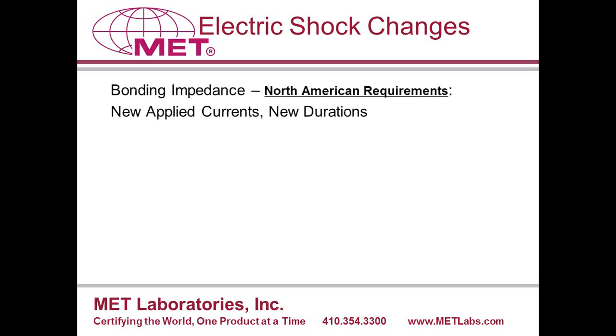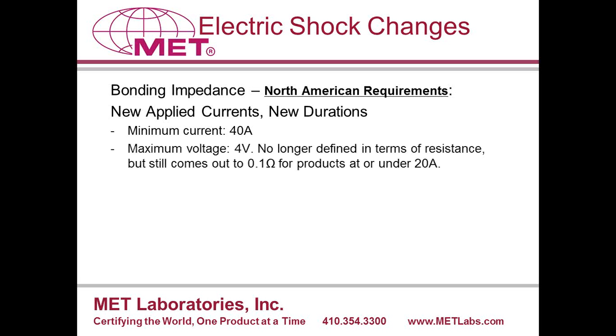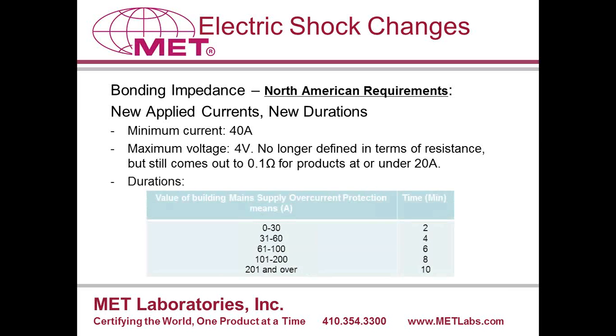Although the bonding impedance test conditions and limits for Europe have not changed, the North American test is significantly more severe. Instead of starting at a 25 amp current, in North America, the test now requires 40 amps, 2 times the trip current of most breakers. Instead of a limit of 0.1 ohms, the limit is now in terms of voltage and may be less than 0.1 ohms if the test current is higher. And instead of 1 minute, in North America, the test requires at least 2 minutes, mimicking the time lapse of tripping the breaker, and increases based on the value of the overcurrent protection.